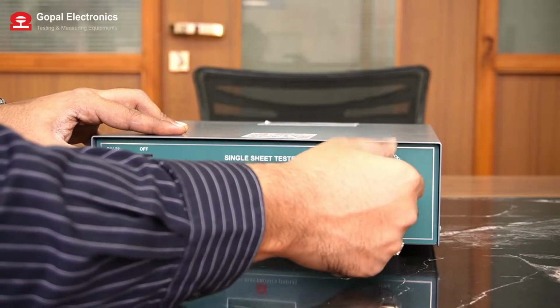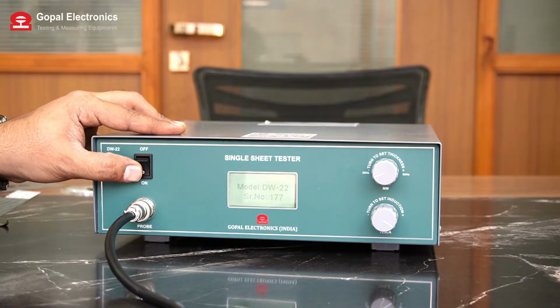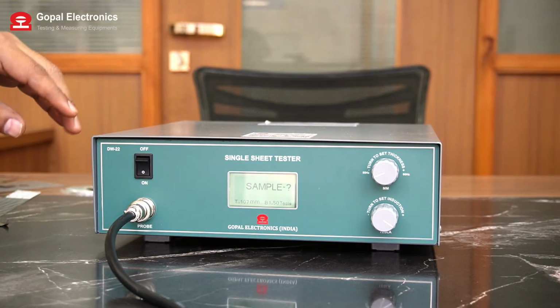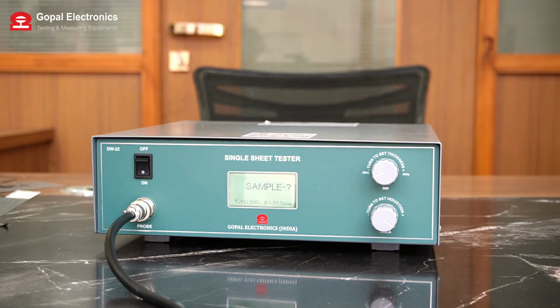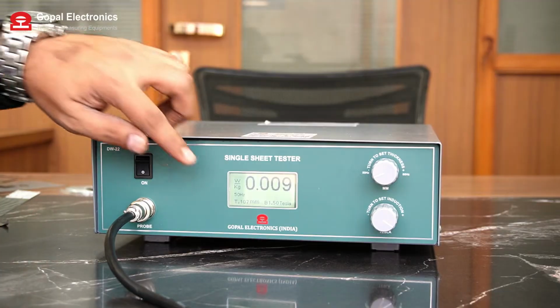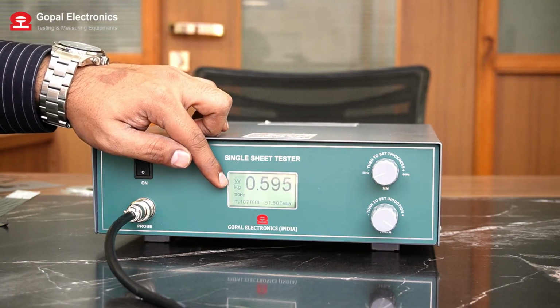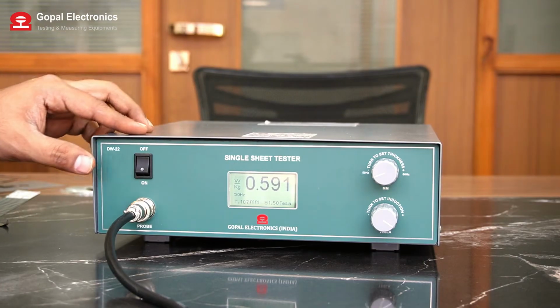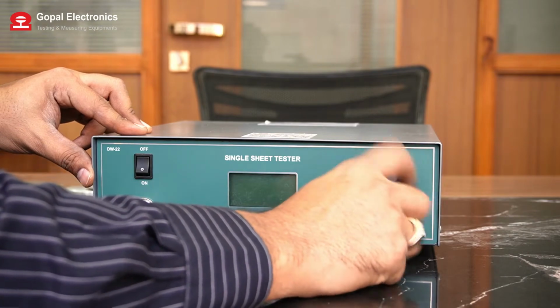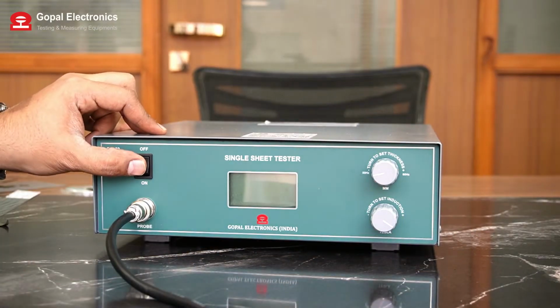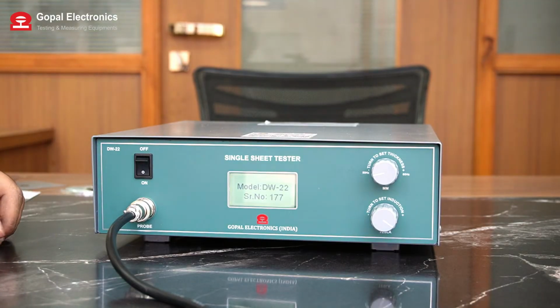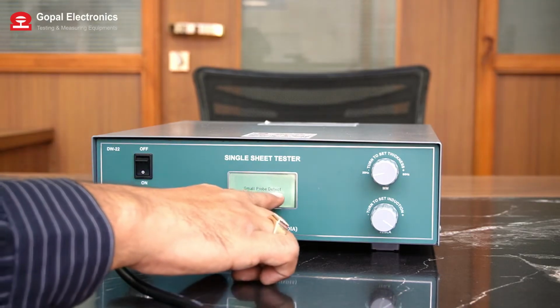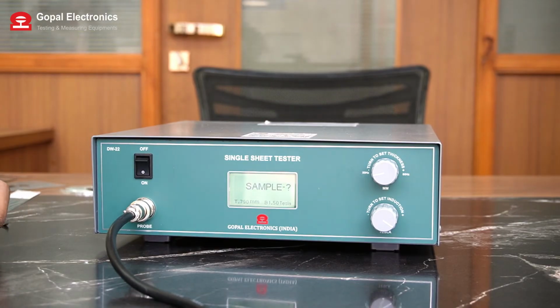If you keep this knob at minimum point for 50 Hz and turn on the equipment, then the set frequency will be 50 Hz. If you want to change the frequency to 60 Hz, you have to turn off the equipment, set it to maximum, at 60 Hz. Now you turn on the equipment. 60 Hz setting done and small probe detected. Now you can place the sample. It will give you a reading at 60 Hz. So this is how you can change the frequency.